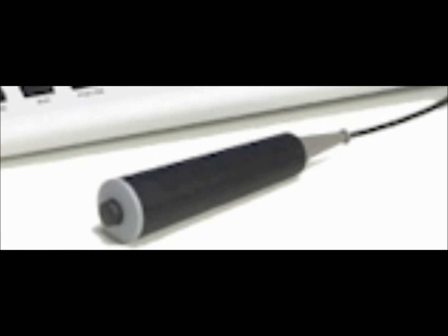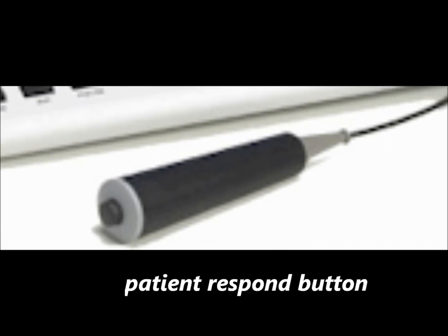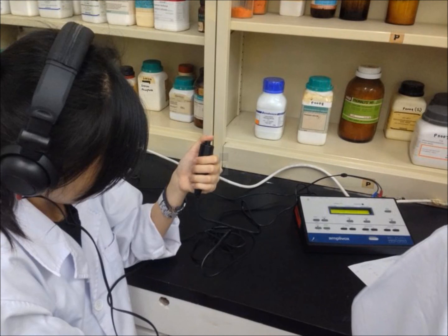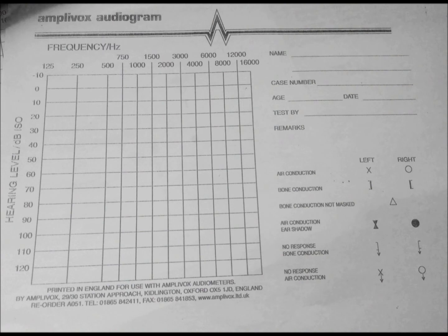Blue color of the headphone will be for the left ear and red color will be for the right ear. We also have here what we call the patient response button. Subject will be asked to hear the sound wave produced by the pure tone audiometer through the headphone. Every sound that is heard by the subject, the button will be pressed to indicate they heard the signal, and the light on the audiometer will light up to let the examiner know they heard the sound, and it will be recorded in the audiogram paper.